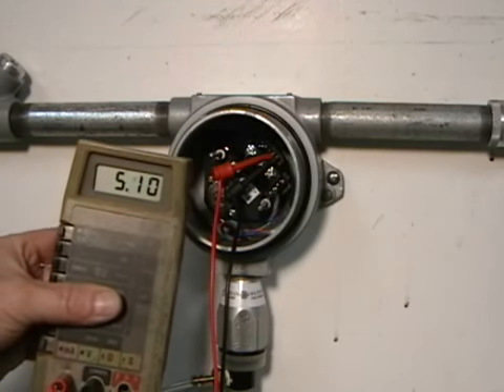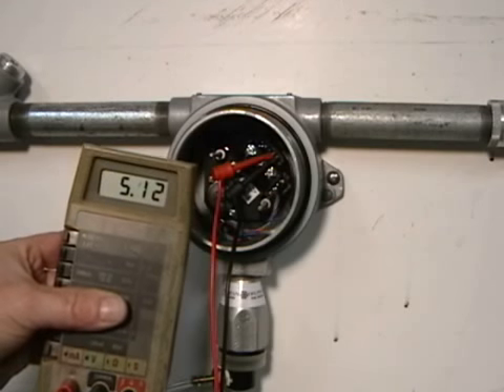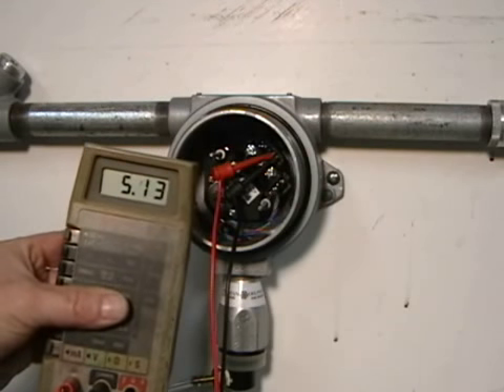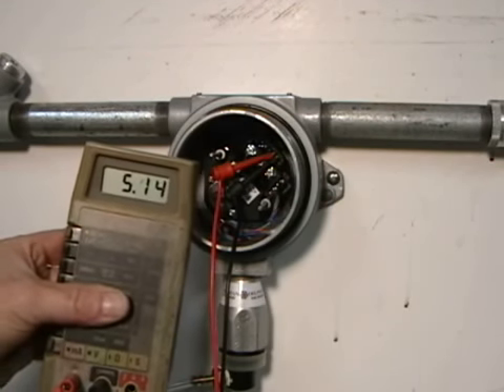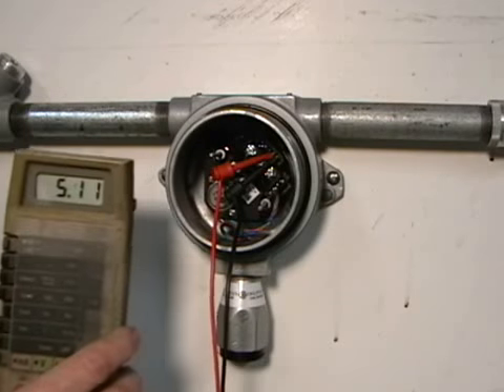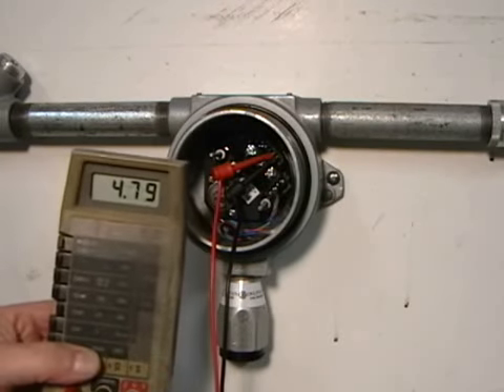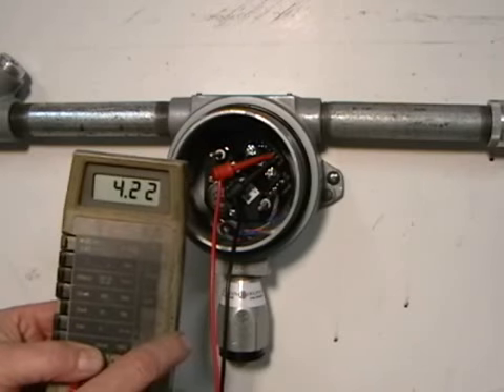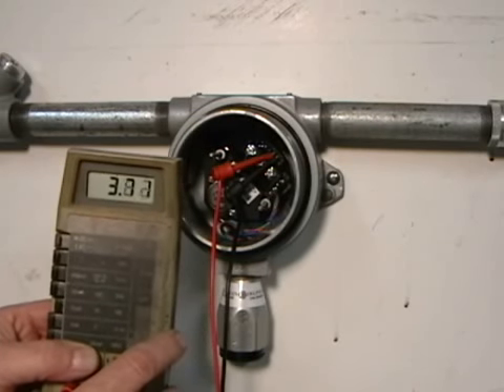In this example, our span is approximately 5.14, giving a delta span of about 2.9 milliamps. This is a perfectly good working sensor transmitter assembly. Now we can remove the gas and watch as the gas dissipates out of the element cavity back to its zero reading.